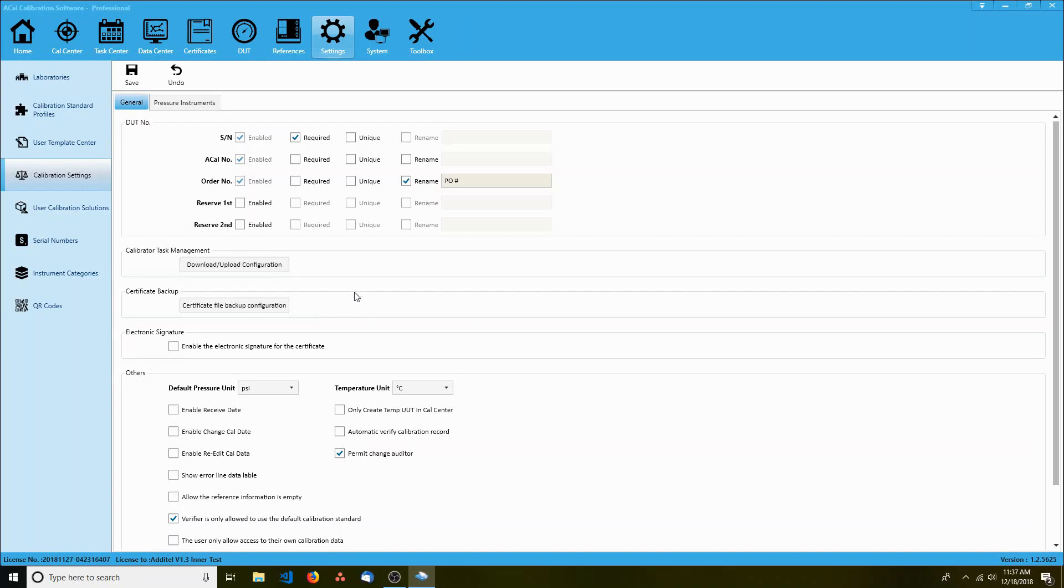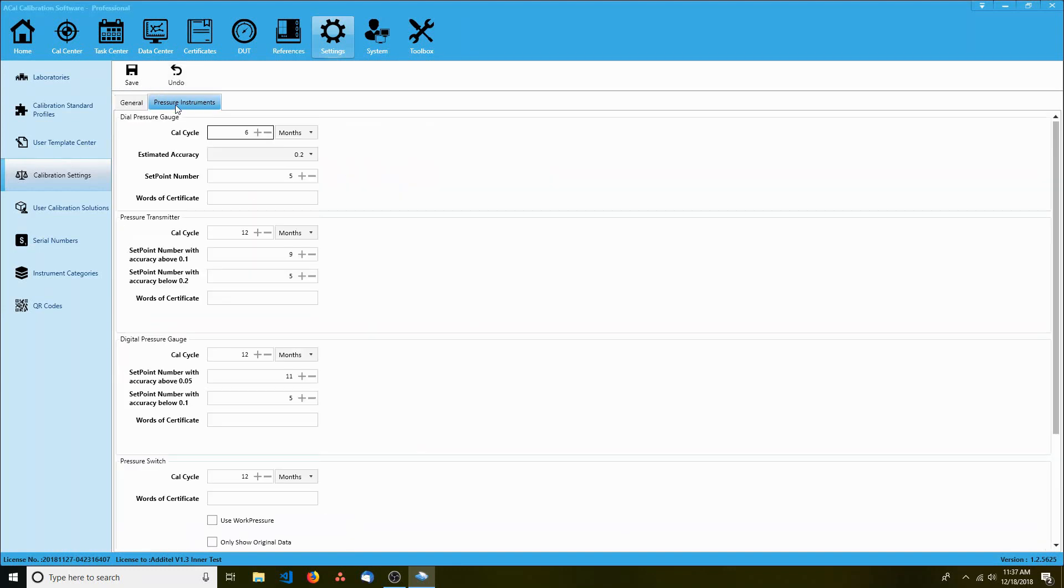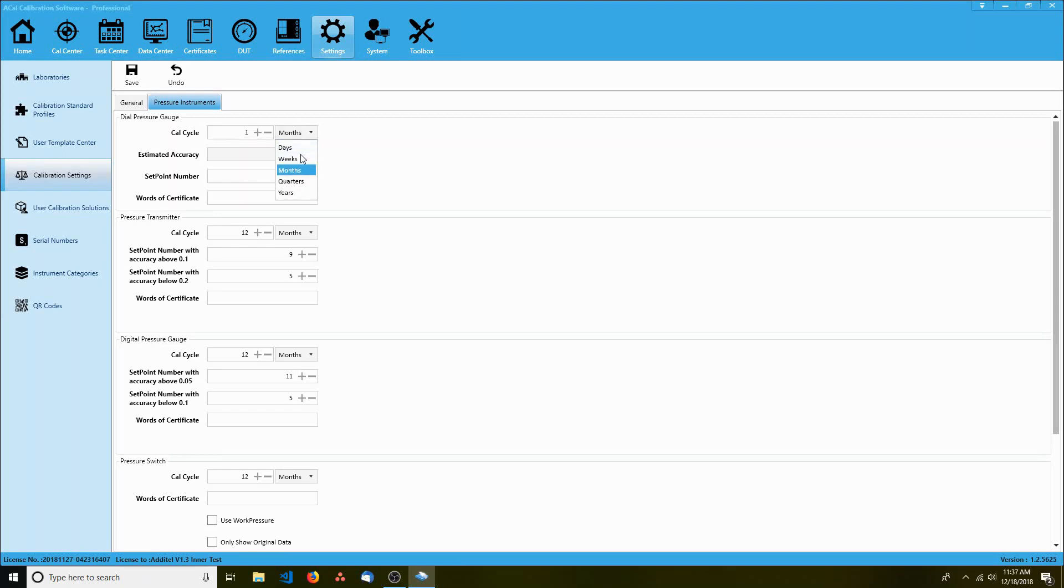Next, go up to the top and switch to pressure instruments. Here you can set the cal cycle lengths for each type of instrument in ACAL. For example, I can set the default due date for dial pressure gauges to be a year after I calibrate them. When you're done with this, click save.